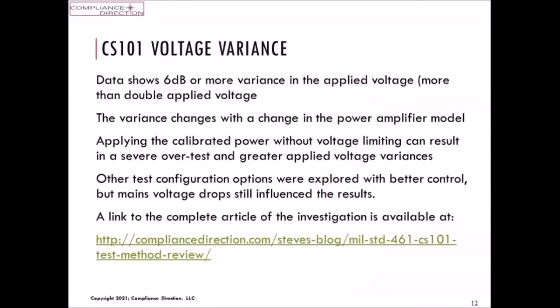This voltage variance, the data shows that there's more than 6 dB variance here, with the variance changes in the power amplifier. Applying a calibrated power without voltage limit gets a severe overtest. It can be 30, 40 dB too much. And we end up burning out traces on the board from an overtest, and it wasn't a legitimate failure. So we cause a failure because we weren't controlling the test adequately. Other configurations were explored. With some associates in Turkey, we did a complete study on this, and that study is there. My associates there did all the legwork on it. I was just an advisory kind of person. But we published an article available at that link, the Compliance Direction website. You can come through my website with the blog and look at that article about it. It'll link to the Interference Technology standard.